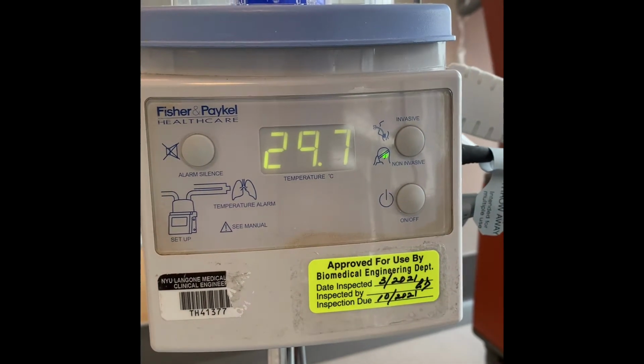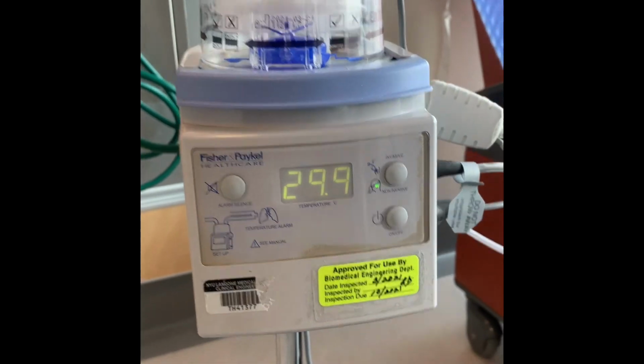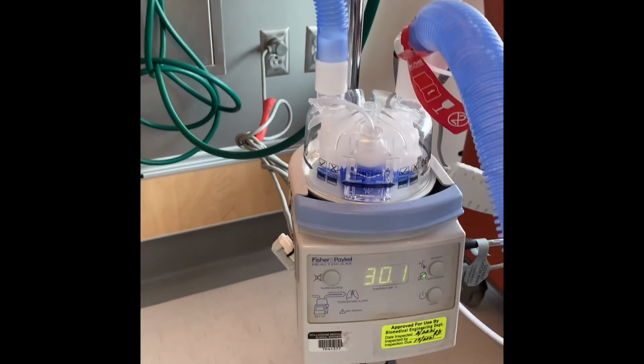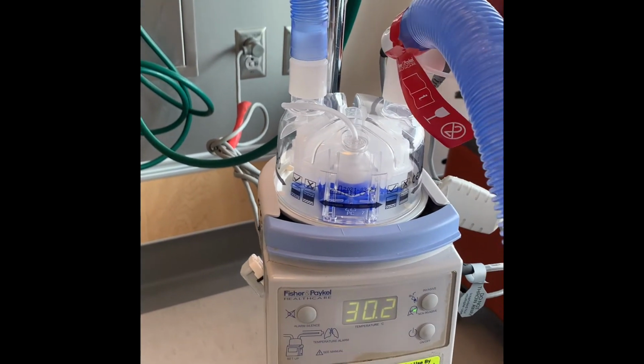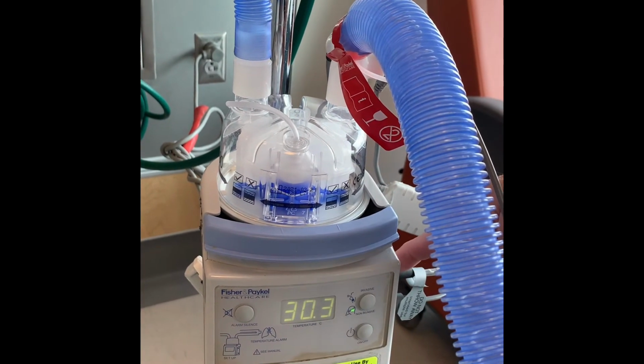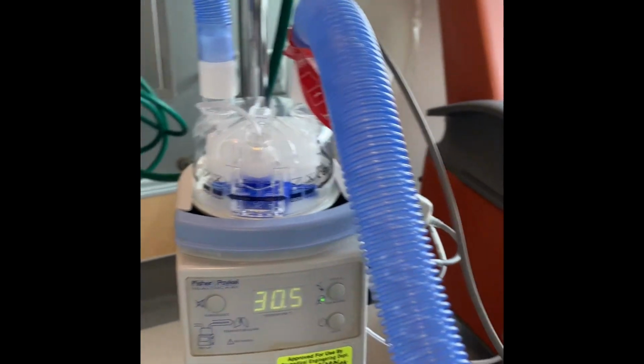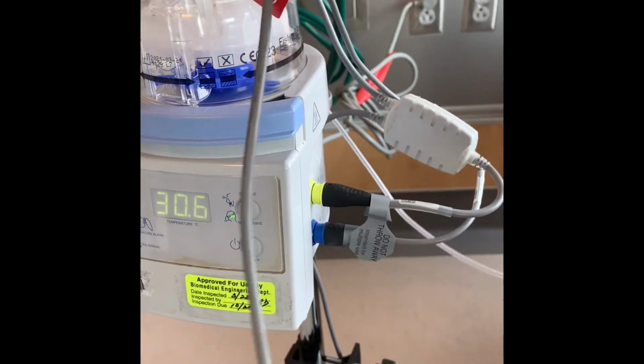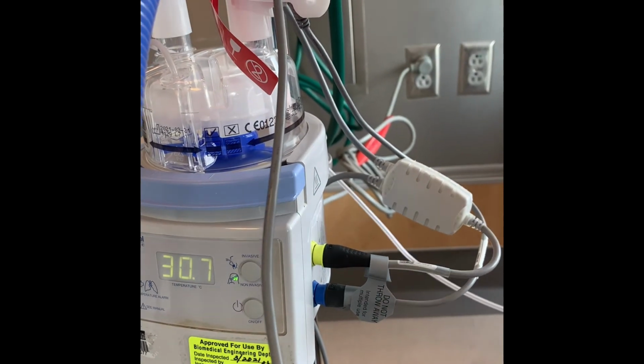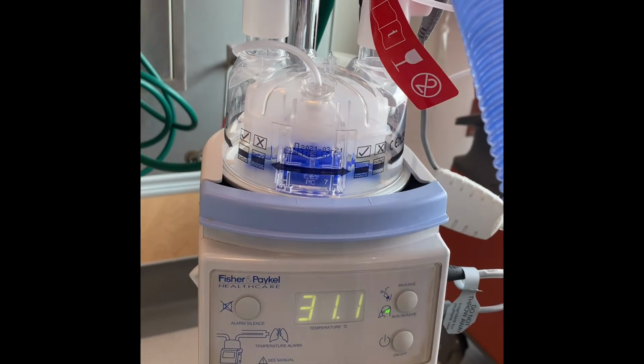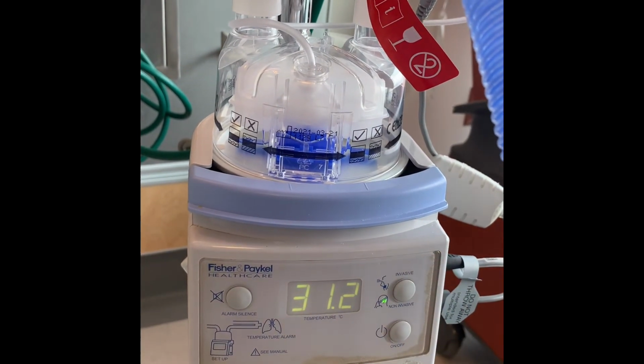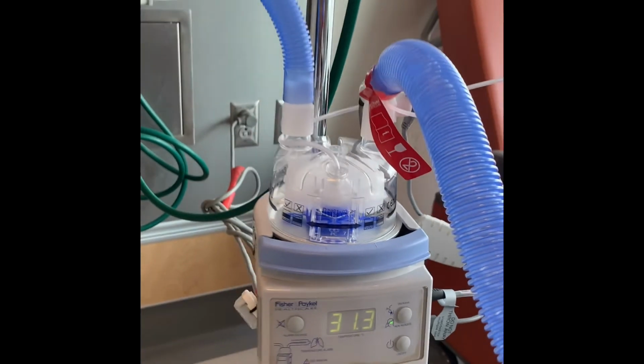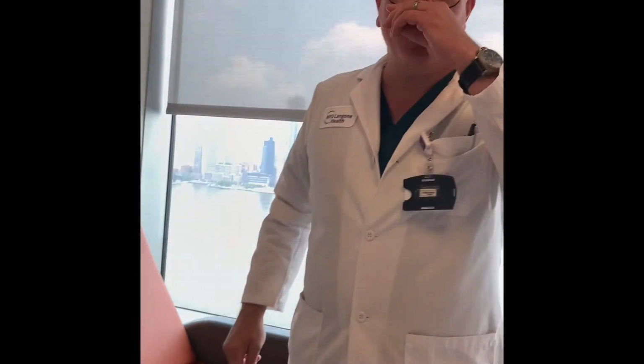Okay, what are reasons this would alarm? If there's excess water in the tubing, it might alarm. Tubing needs to be drained. Sometimes the main reasons this would alarm is if the actual pigtail wasn't working, or the circuit was broken inside of the machine, or the temp probe, something was wrong, defective. Those are the main reasons. I'd expect to see this temperature in non-invasive at 32, which it's working its way up to now. Oh, and if there's no water, like we don't have water, eventually this would start alarming because we haven't spiked the bag for water. But if it's spiked with water, it shouldn't give you any problems.